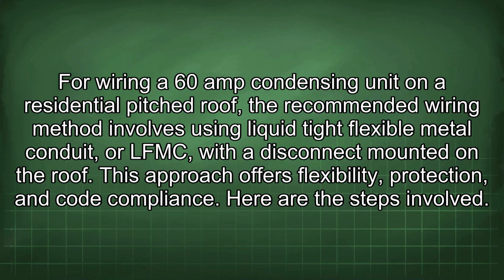For wiring a 60 amp condensing unit on a residential pitched roof, the recommended wiring method involves using liquid-tight flexible metal conduit, or LFMC, with a disconnect mounted on the roof. This approach offers flexibility, protection, and code compliance. Here are the steps involved.